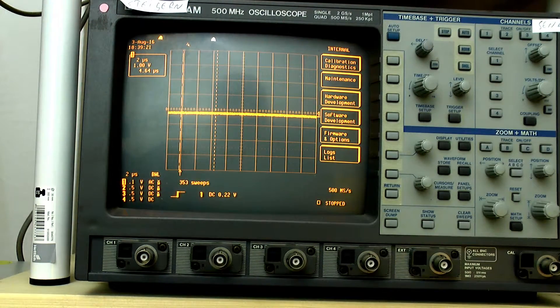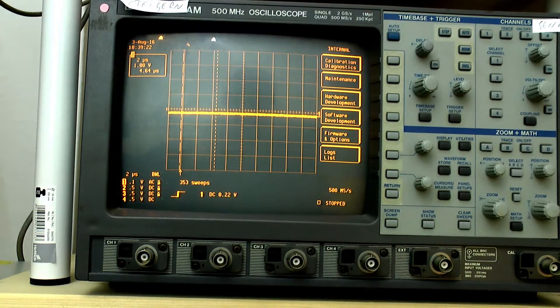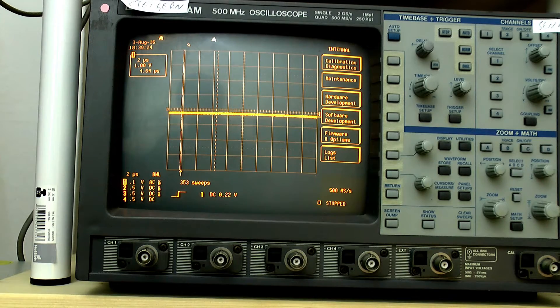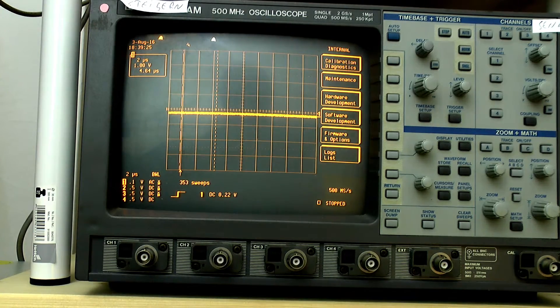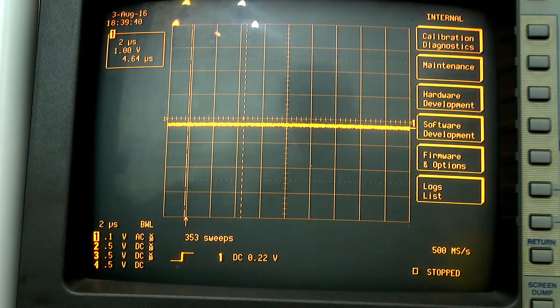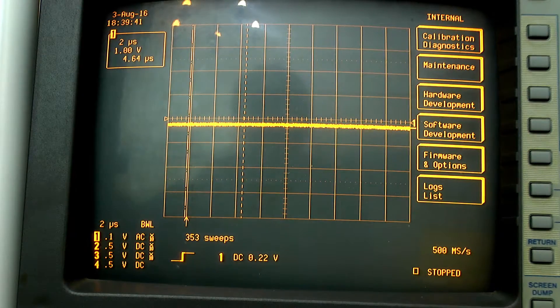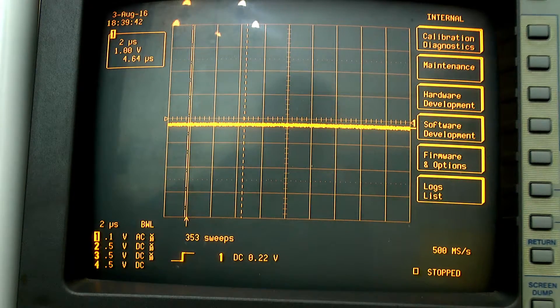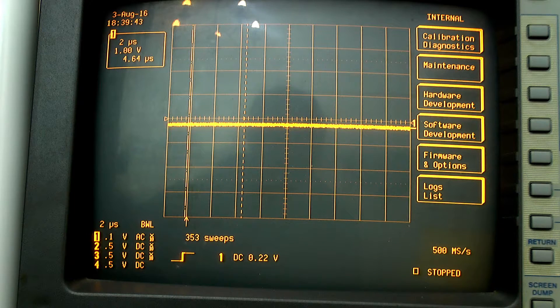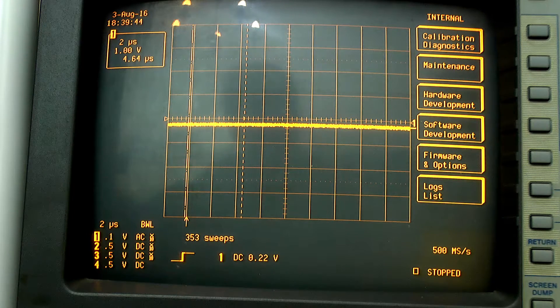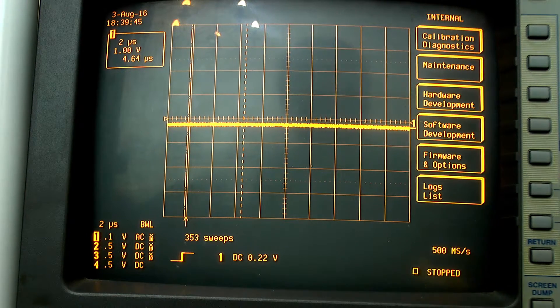And tada, you see that you're inside the calibration menu. The actual handling of the maintenance menu is very similar to that of the rest of the scope.